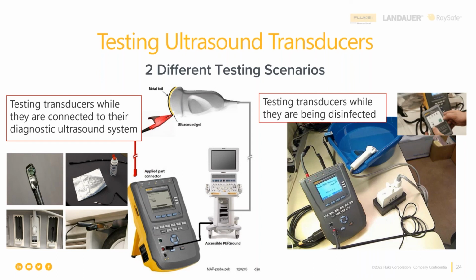Either of those scenarios needs the leakage current value to go along with the transducer when it's sent out for repair. In order to do that, because the connections on the ULT are different from the connections along the top of the safety analyzer, we provide this little pigtail adapter, and you need two of them, one for your test lead and the other for your transducer adapter, which is specific to the connector used for that transducer on its diagnostic ultrasound system.